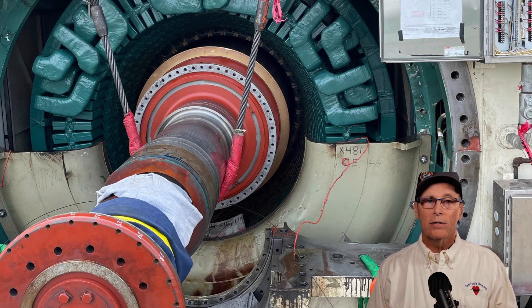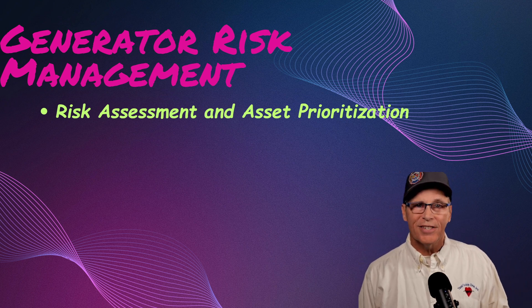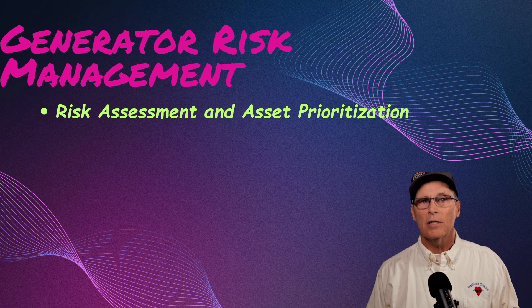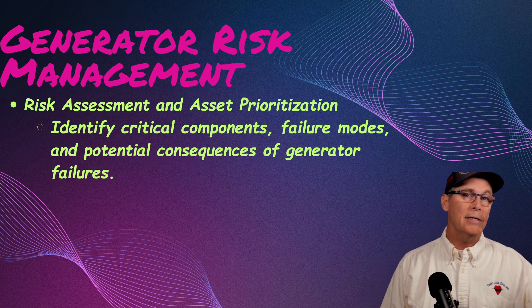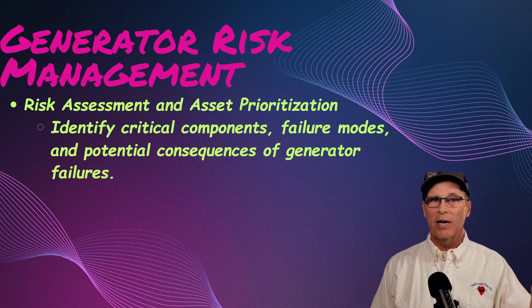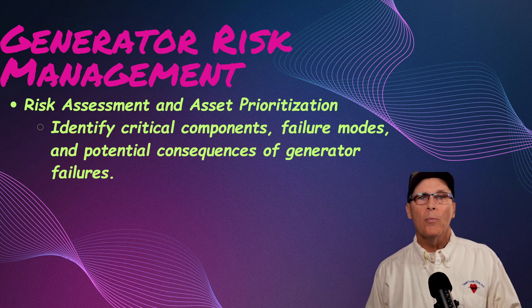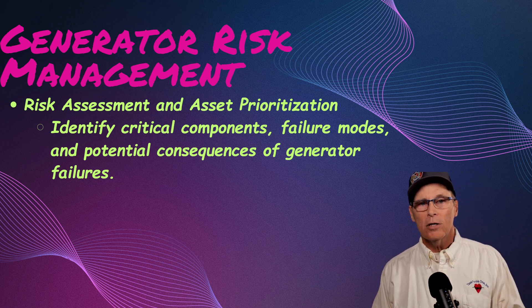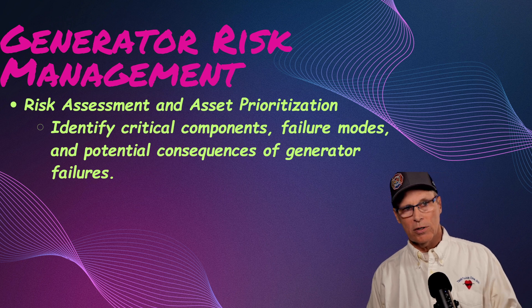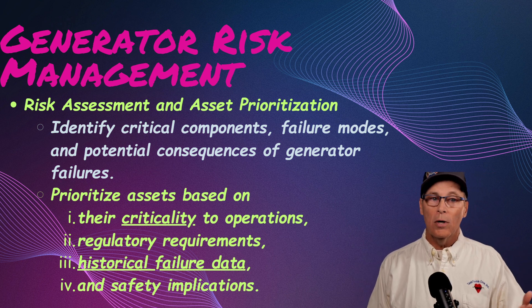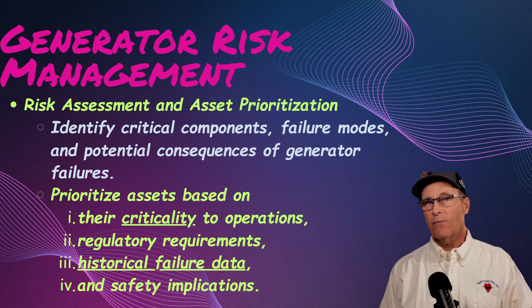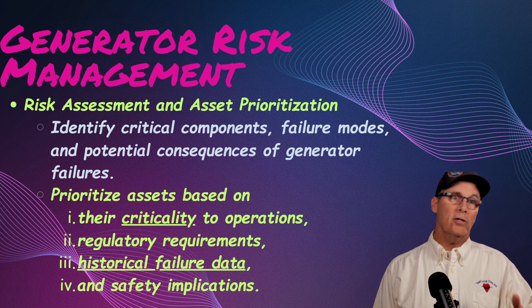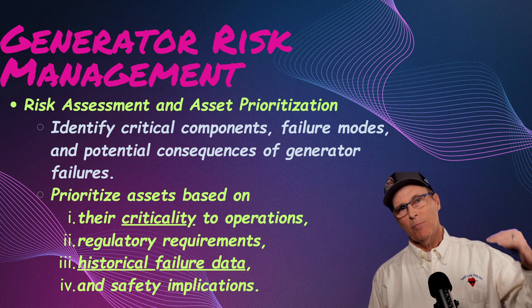Here's a close-up of a field getting ready to be pulled out of the stator. Now let's talk about managing the risks. We need to assess risks and prioritize assets — figure out which units are most important, which ones would shut down the entire plant. In a refinery or petrochemical facility, you may have redundant power generation or be able to rely on the grid for a while. Determine your most critical assets, then prioritize based on criticality, regulatory requirements, contractual obligations, and historical failure data. If a machine has known fleet issues elsewhere, that raises its priority.